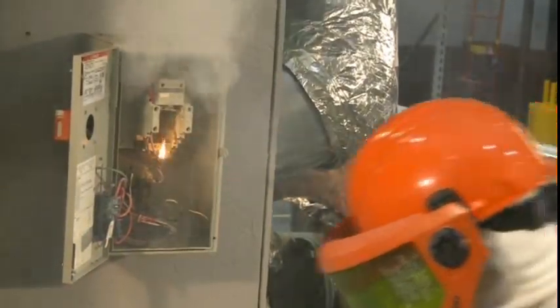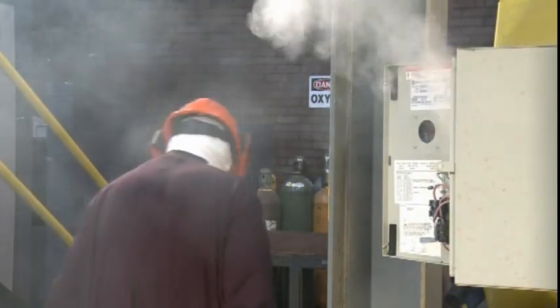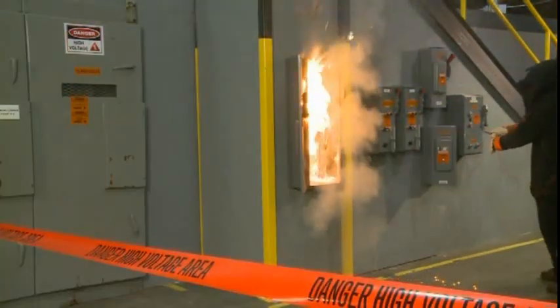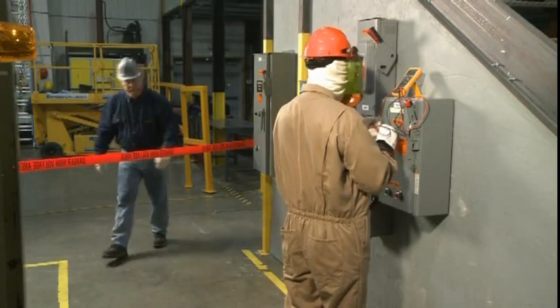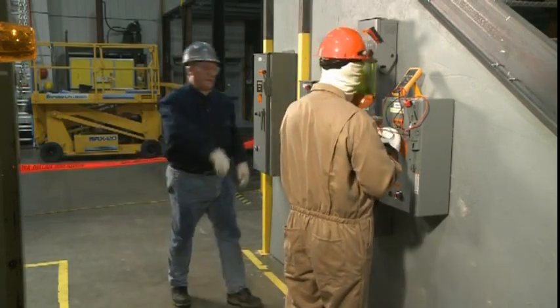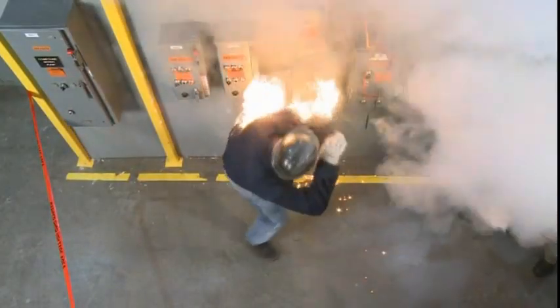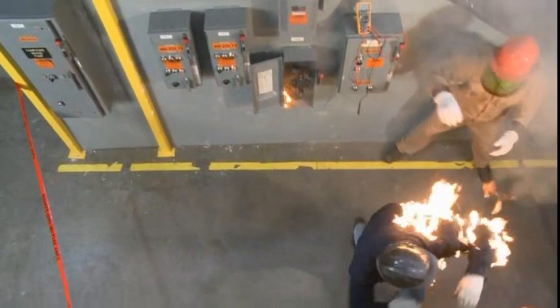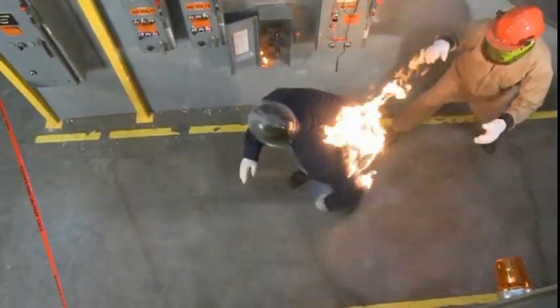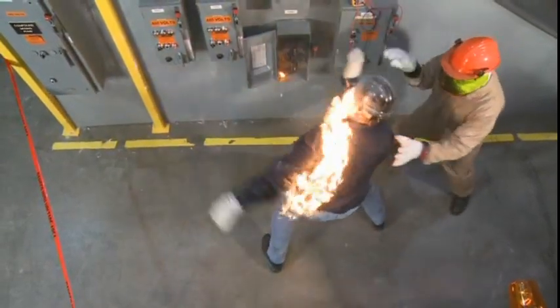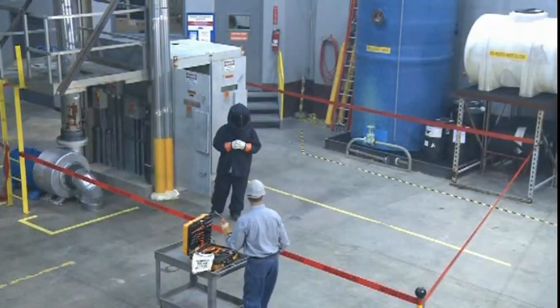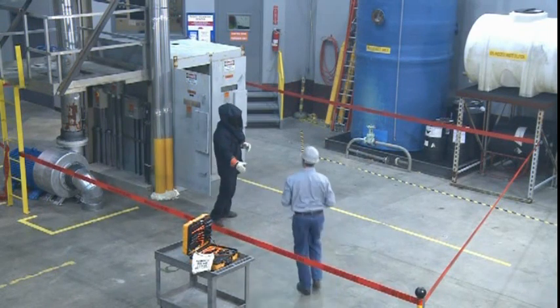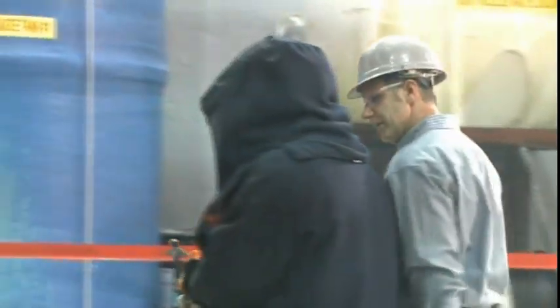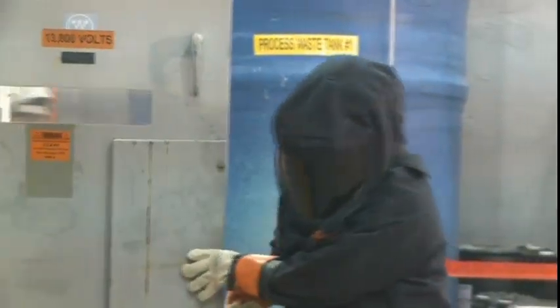Arc-rated clothing is designed to withstand both the intense heat and force of an arc blast without breaking open or bursting into flames. Clothing that is not arc-rated, such as 100% cotton or wool, can burst into flames and continue to burn even after the arc is extinguished. When unprotected workers cross the arc flash boundary without arc-rated clothing and protective equipment, they place themselves at risk of serious burn injury.